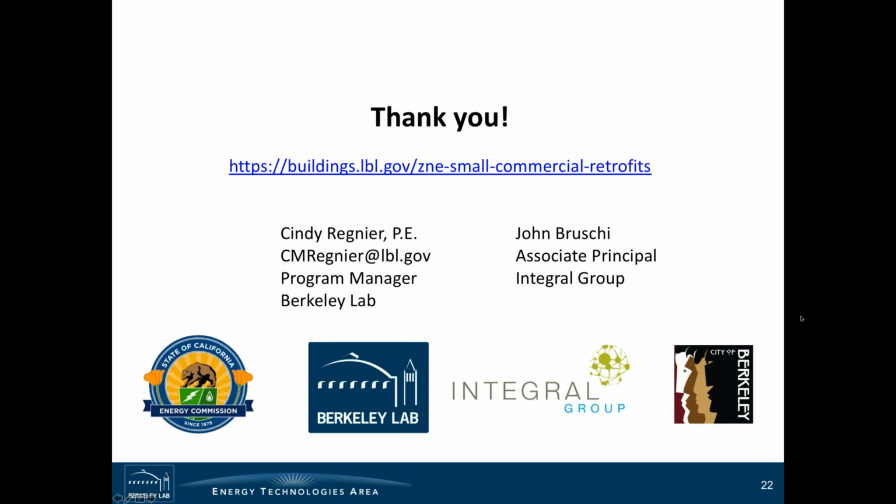Let me move on to the next one. Can you detail a little more the specifics for the package A and package B measures and why such a difference in performance? I think what they're referring to there are the two standard retrofit packages. We will have a very detailed report coming out that will get into the specifics on those, but I mentioned at the top that the key differentiator for those two, package A and package B, is the standard retrofit cases. Package A was a VAV rooftop unit with gas heat, and package B was a VAV DX cooling only unit that was coupled with a hot water boiler that then worked with VAV reheat boxes.